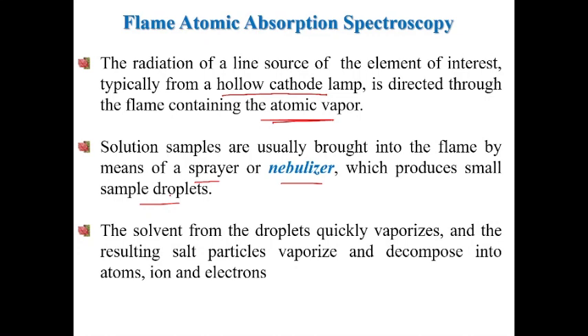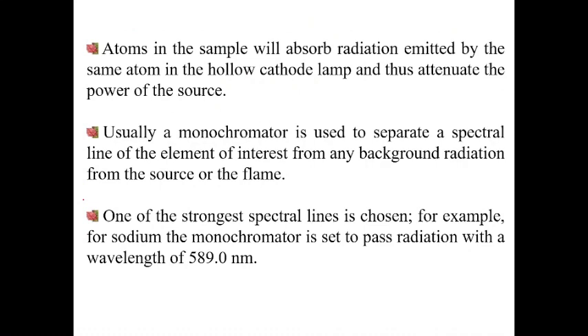Some atoms get excited and some get ionized during atomization. Atoms in the sample absorb radiation emitted by the same element in the hollow cathode lamp. The cathode of the hollow cathode lamp is always made of the element whose concentration is being determined — for example, if determining iron content, the cathode is made of iron. Attenuation of the radiation is then measured. A monochromator is used to separate the spectral line of the element of interest from any background radiation. For sodium, the monochromator is set to pass radiation at 589 nm.